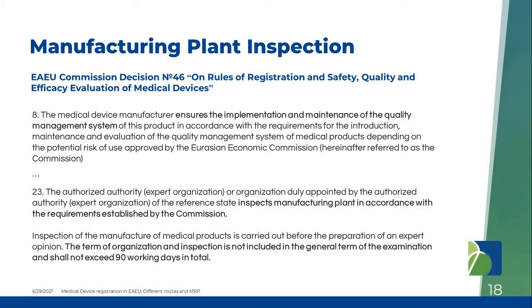And the authorized authority or expert organization duly appointed by the authorized country inspects the manufacturing plant in accordance with the requirements established by the Commission. Inspection of the manufacturer of medical products is carried out before the preparation of the expert conclusion, as I said before. And the timelines for inspection are not included in the total timelines of the registration process, but should not exceed 90 working days in total.